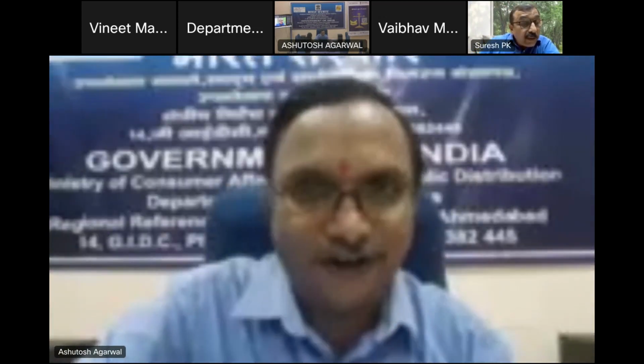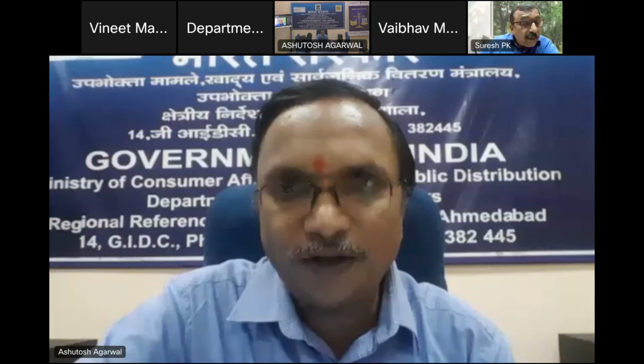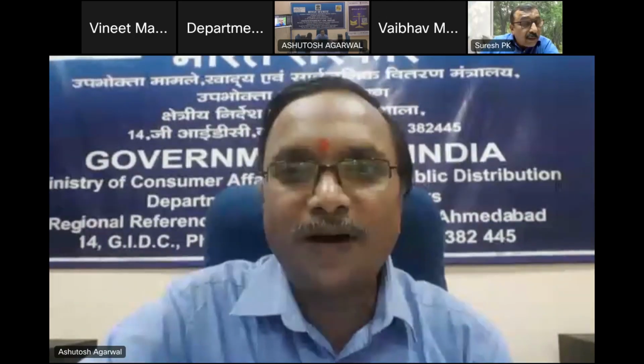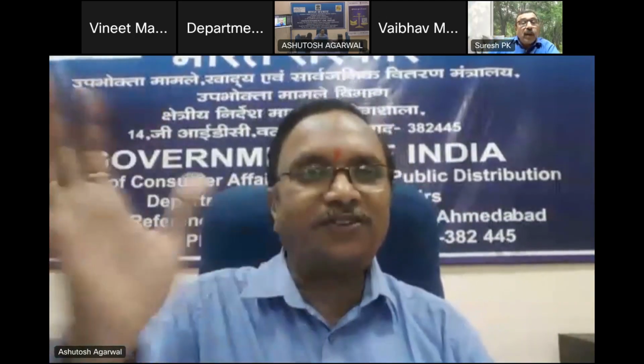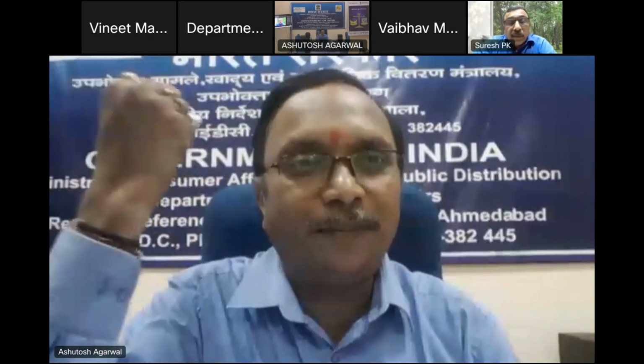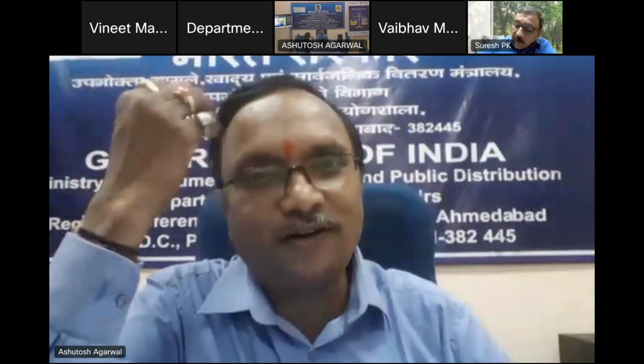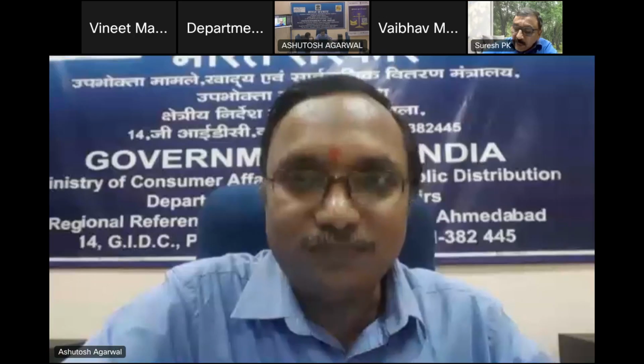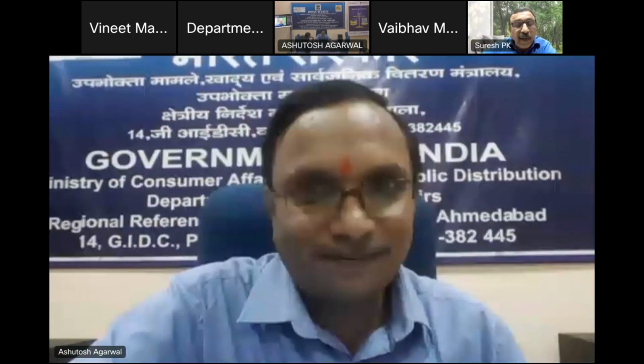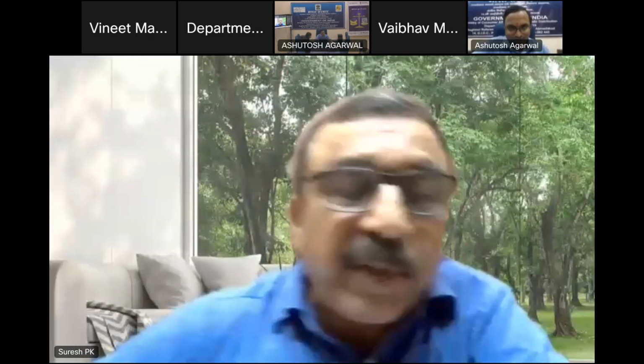Of which, uncertainty is taken in part for the calibration method of the master meter method. Suppose somebody is calibrating through a master meter, what are the parameters which will affect the uncertainty? The first is the master meter uncertainty. The master meter is getting calibrated somewhere, so the calibration certificate of the master meter will mention that uncertainty. You have to take that into account. Then you have to take into account your system, the type A uncertainty of your system.